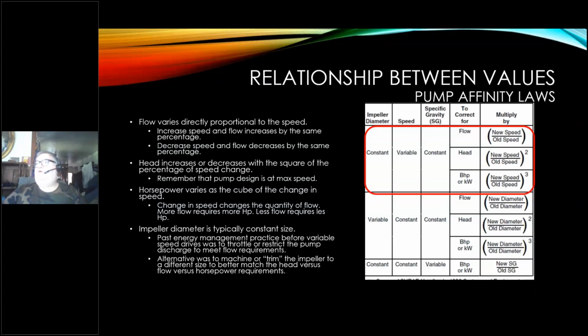And remember that the flow varies directly proportional to the speed. So I have a constant, and now this is the interesting part, a constant impeller diameter. Why would I even think about a variable impeller diameter? I'll tell you in a moment. The speed can be variable. My specific gravity, basically the fluid that I'm pumping, is constant. In this case, water is 1. If I want to correct for flow, the flow changes directly as the speed changes. Double the speed, double the flow. Half the speed, half the flow. Okay, simple. However, when we start talking about the head the pump can produce, it will increase if I change speed by the square, and it also decreases by the square. So we'll have some examples about this.